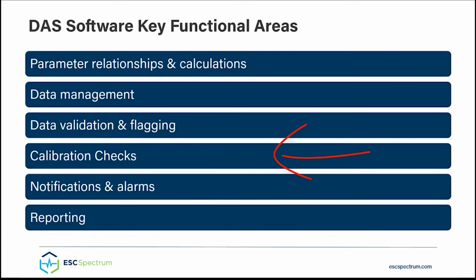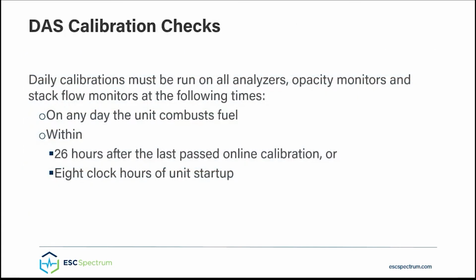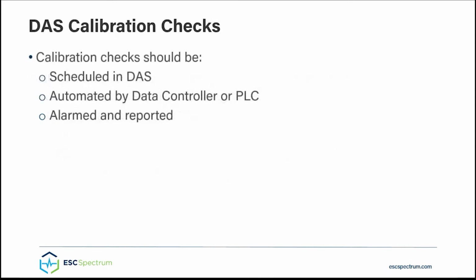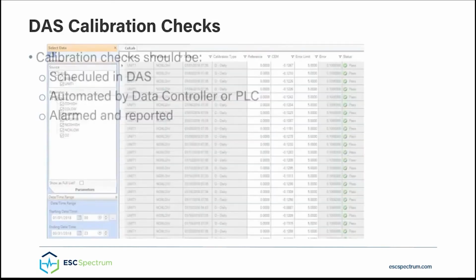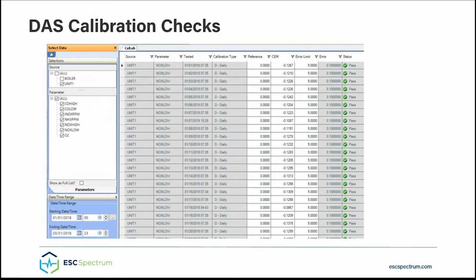Now let's take a look at calibration checks. Part 75 requires that you run daily calibrations on all operating days and within 26 hours after the last successful online calibration and within 8 hours of startup. Your DAS should be capable of automating your daily calibrations and should allow you to manage daily calibration checks, change data such as the reference values and actual values, and reevaluate calibration errors. In StackVision, CalLab provides this functionality and manages 7-day calibration error tests, offline calibration demonstrations, and cycle/response time tests.